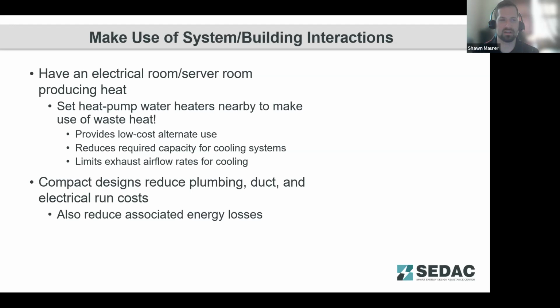When looking at building interactions, do you have a high heat source like an electrical room or an electrical closet that's producing a lot of heat? Then you've got a heat demand in the building like domestic hot water or kitchen water, something like that. Can you look at the potential to recover heat from those high heat spaces through a heat pump system and use that as a means to recover that energy that would otherwise be exhausted out of the building through an exhaust fan? Those can help improve the efficiency overall of those systems and design.